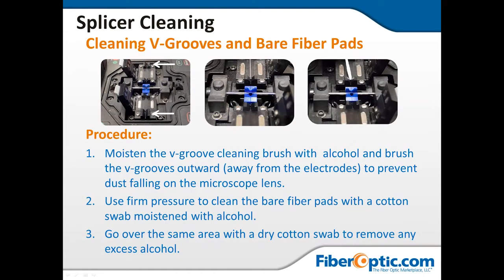Procedure. 1. Moisten the V-groove cleaning brush with alcohol and brush the V-groove outward, away from the electrodes. This is to prevent dust from falling on the microscope lenses. Use firm pressure to clean the bare fiber pads with a cotton swab moistened with alcohol. Go over the same area with a dry cotton swab to remove any excess alcohol. So you make sure you just always have 2 with you when you're cleaning the V-grooves.